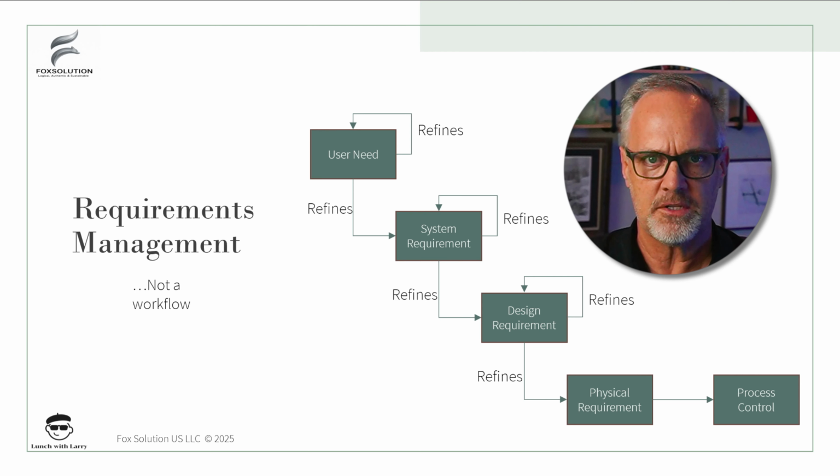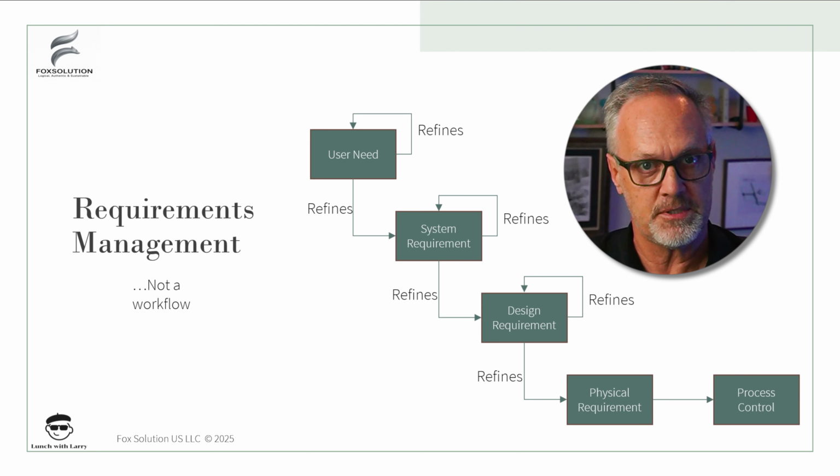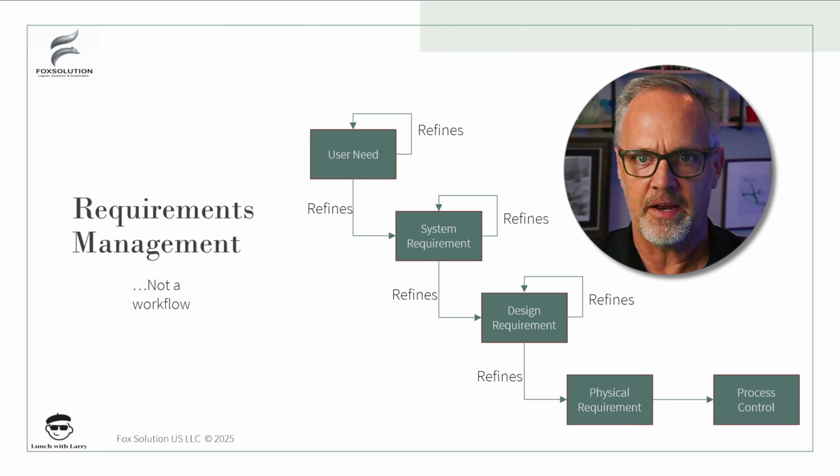So system requirements, we have systems and subsystems and sub-subsystems, right? Very commonly, we might have 5 different levels of system requirements or only one level. So this is also an example of where we need a parent-child relationship. The final one here is design requirements, and typically the way that goes is we have design requirements that are things like the device will include the following colors, and then a requirement that it'll include orange. And those levels of requirements are convenient and oftentimes carried in the standards, so it's kind of nice to have this ability to nest our design requirements as well.